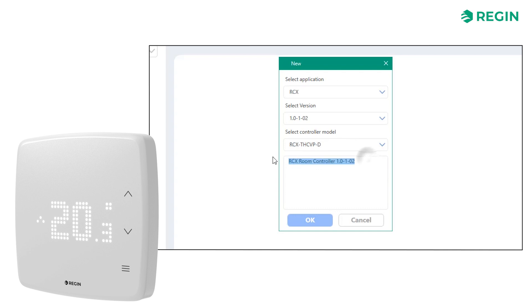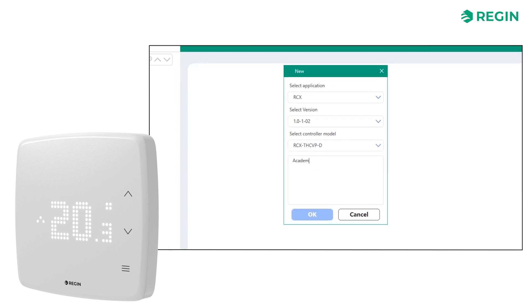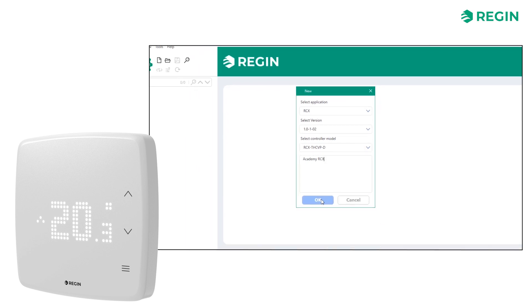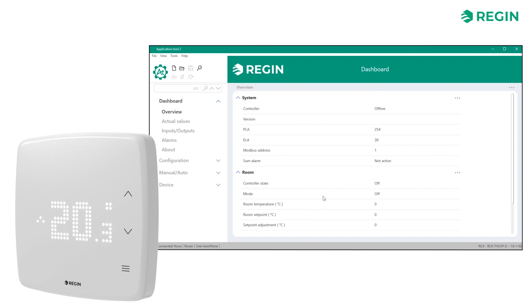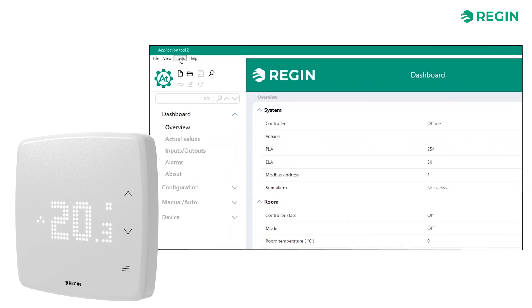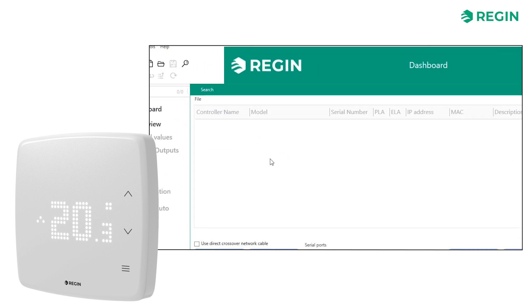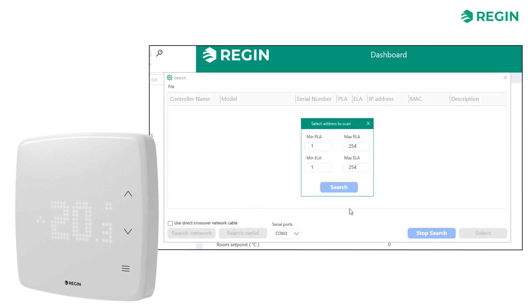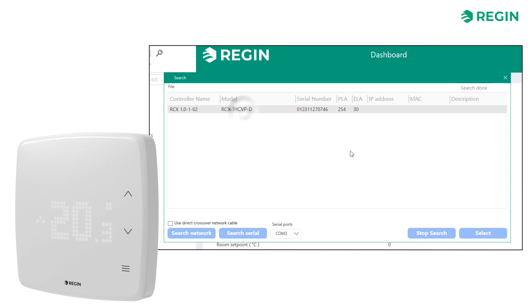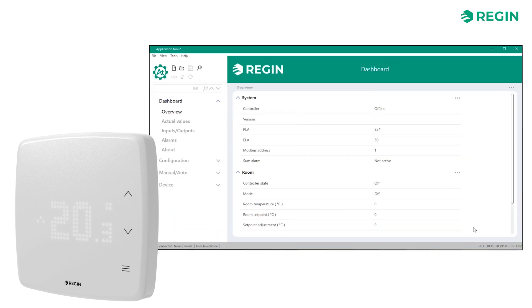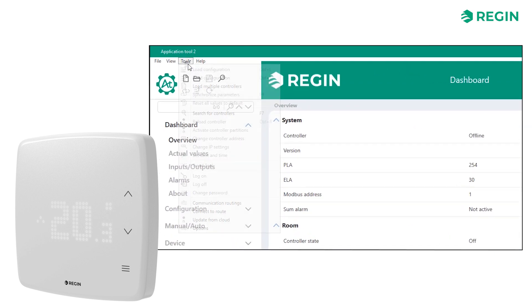In this example, we are using an RCX-THCVP-D — a model with a full complement of built-in sensors and a display. You can then use the Search Serial function to identify and connect to your Regin RCX controller. Application Tool 2 will prompt you to download any available software updates, ensuring you will be working with the latest release and able to update the controller firmware if necessary. To manually check for updates, go to Tools and Update from Cloud.